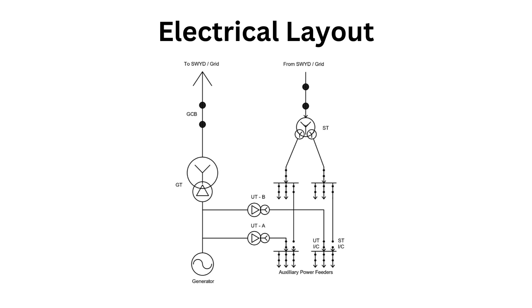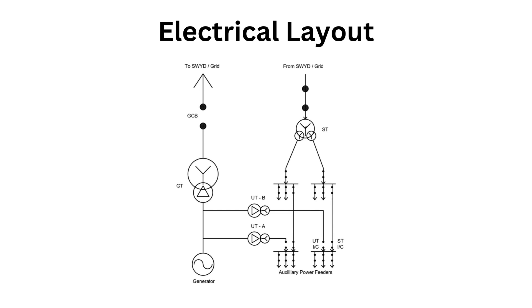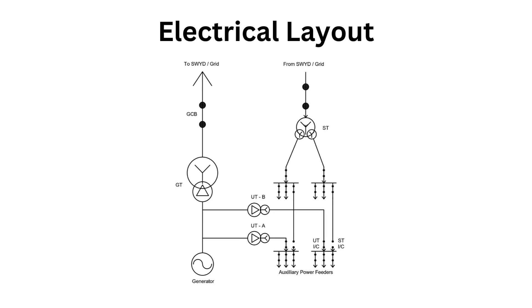You may wonder what happens when the generator is not in operation. At that time, power will be fed by the Station Transformer, which takes power from the grid. When the generator starts generating power, the unit bus is charged through the Unit Transformers and the incomer from the station bus is opened. This changeover is named the UT/ST changeover.